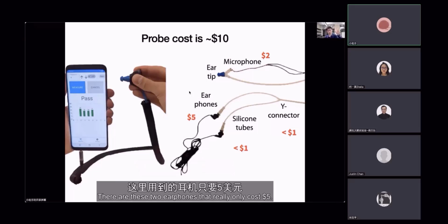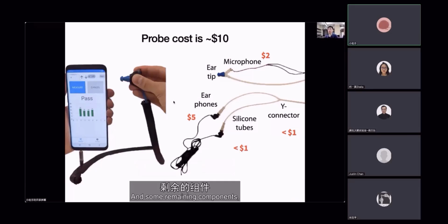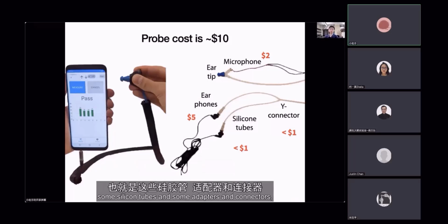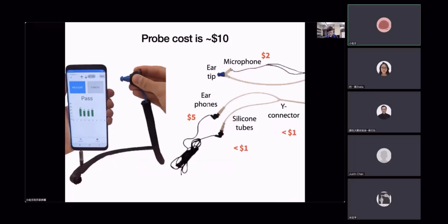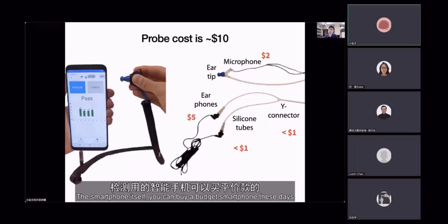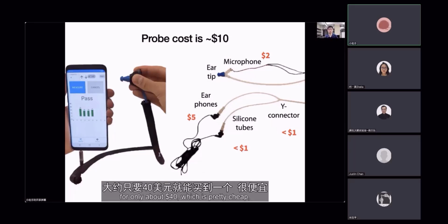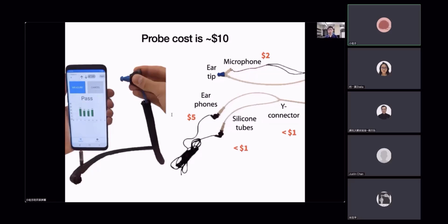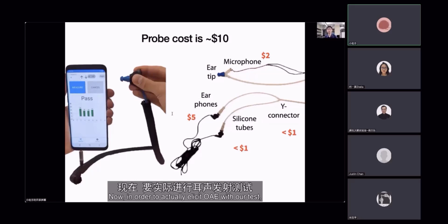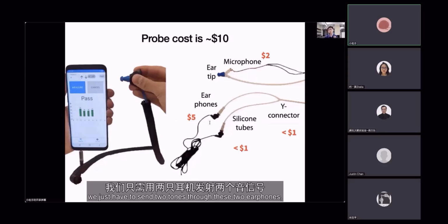And we designed a low-cost probe using off-the-shelf components. It costs just about $10, and you can see the price breakdown here. There are those 2 earphones that only cost $5, the microphone which costs $2, and some remaining components, some silicone tubes and some adapters and connectors that cost only about $2 in total. The smartphone itself, you can buy a budget smartphone these days for only about $40, which is pretty cheap, making the total cost of this device only about $50, which is a pretty large decrease compared to some of these conventional devices, which can cost upwards of $6,000, which is over 100 times more expensive.